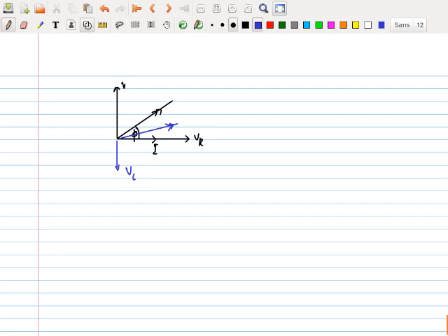Then they put an automated capacitor bank so that they can make this almost equal to a resistor. Because why? If they don't, they get charged for reactive power. So they put a capacitor bank in front so that this one which is vertical is negated by the other one which is going at minus 90, so that the entire thing becomes resistive. Right?